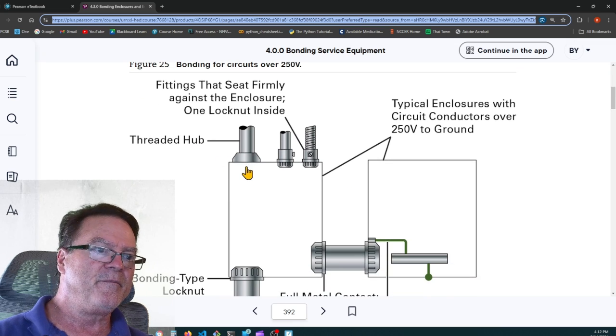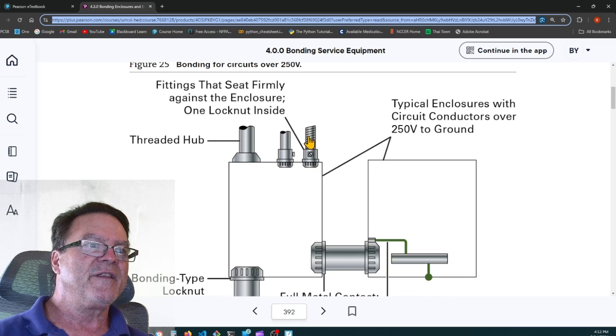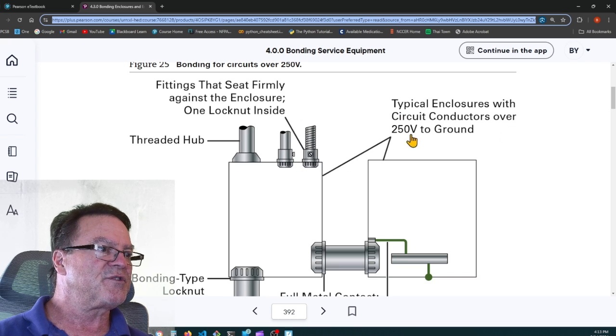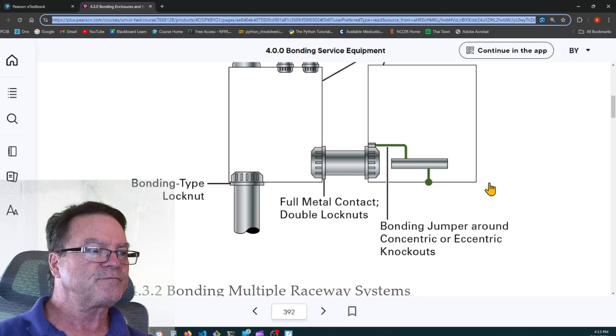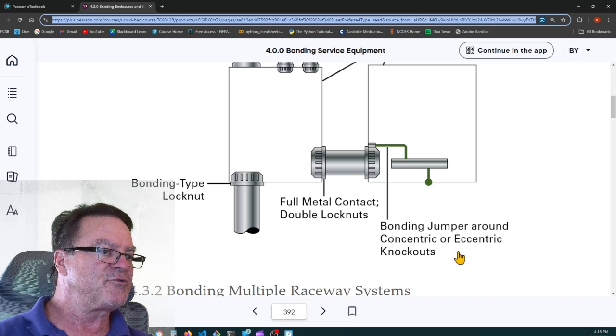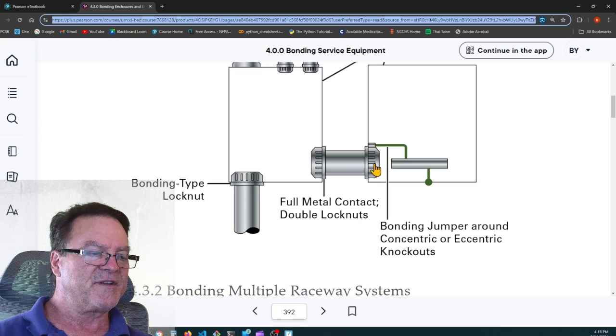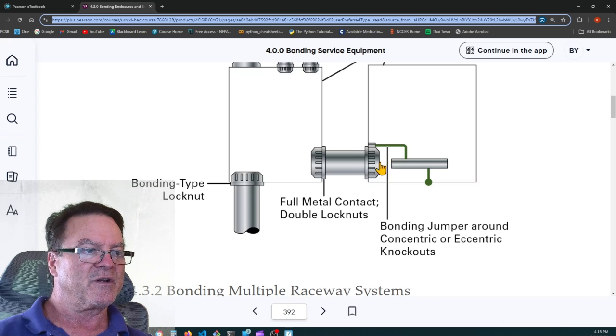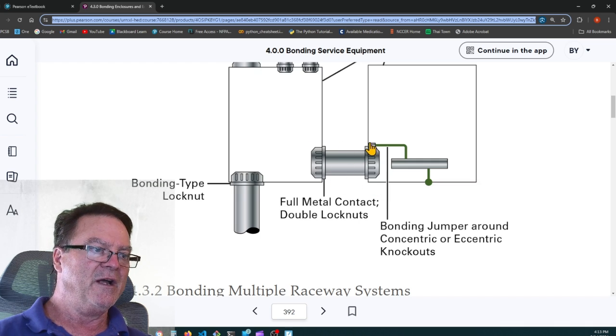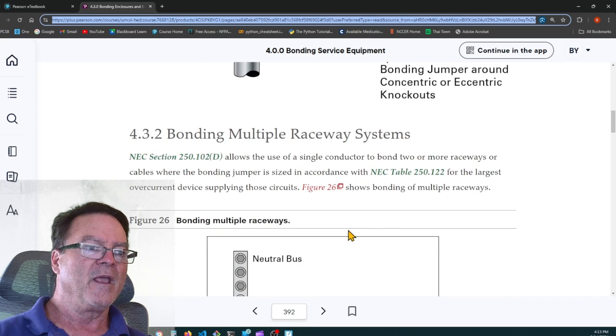So you can use a threaded hub. You can use a fitting that seats firmly against the enclosure, or one lock nut inside the enclosure. Typical enclosures with circuit conductors over 250 volts. There's a bonding jumper around the concentric or eccentric knockouts. If you're using knockouts that are factory installed, eccentric or concentric, you have to put a bonding bushing on your conduit nipple and take it to the grounding bus. Here's a bonding type lock nut, full metal contact double lock nut.